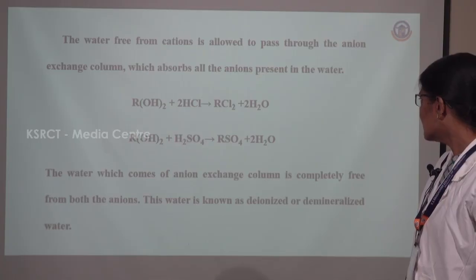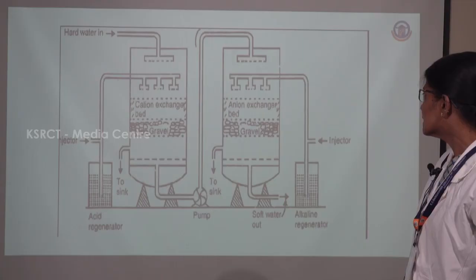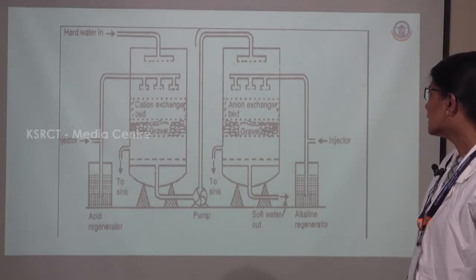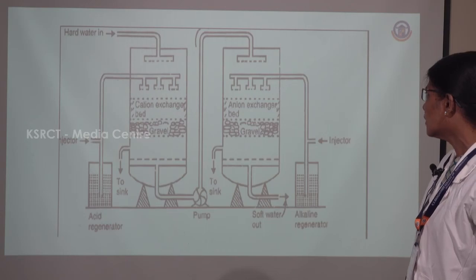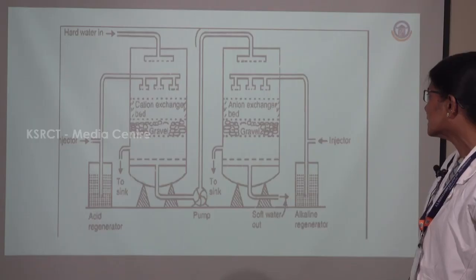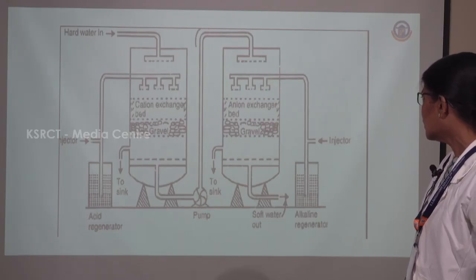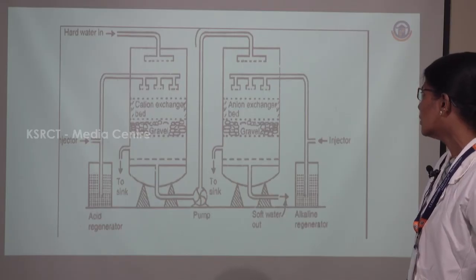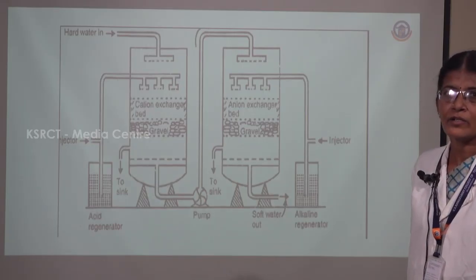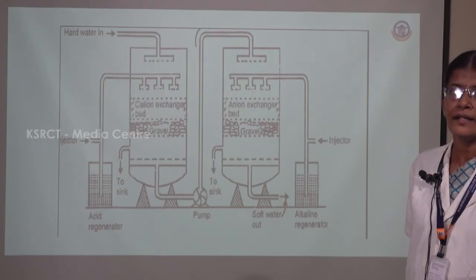The water coming out from the anion exchange column is completely free from anions and is known as demineralized water or deionized water. The picture shows the removal of cations and anions: the first column is packed with the cation exchange resin, the second column with the anion exchange resin. Hard water enters through the inlet; through the second column's outlet, soft water is collected. In the first column cations are removed, in the second column anions are removed, and the resulting soft water is totally free from both cations and anions.